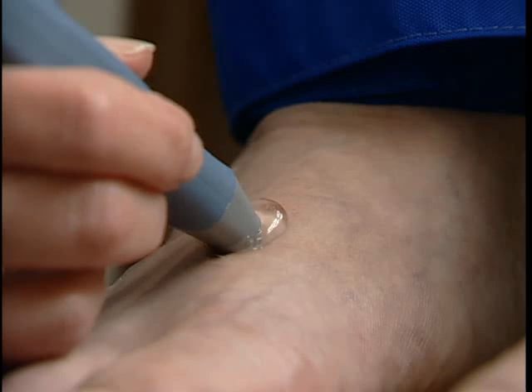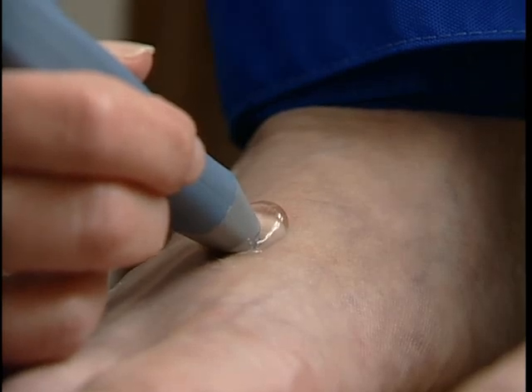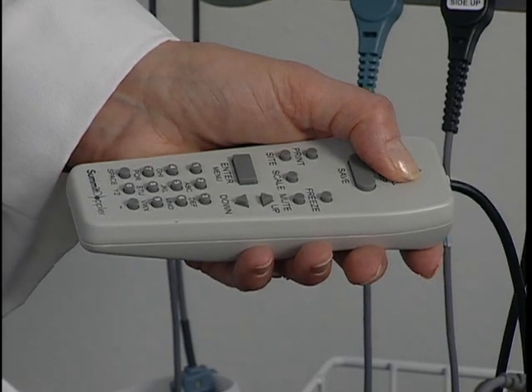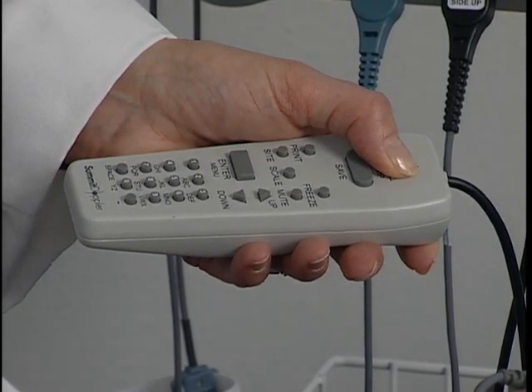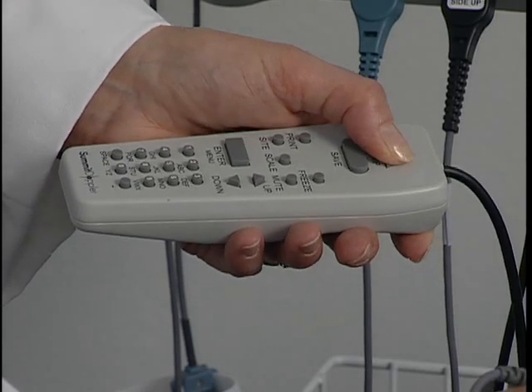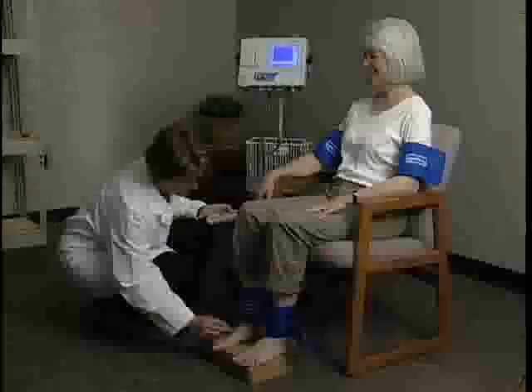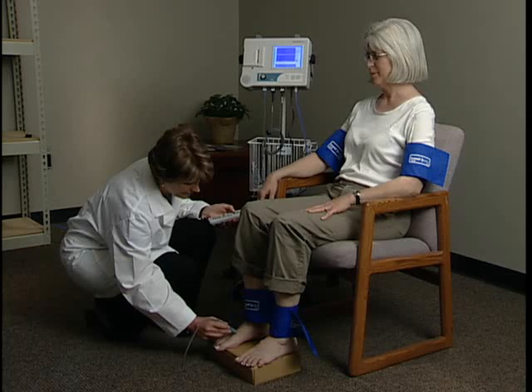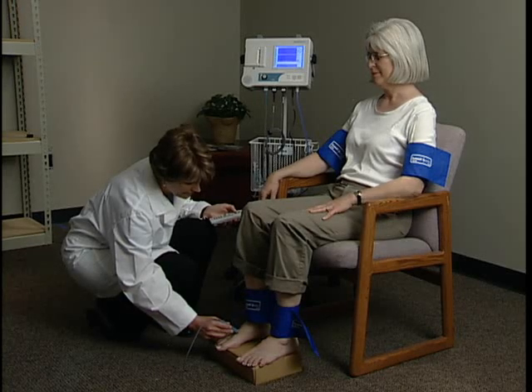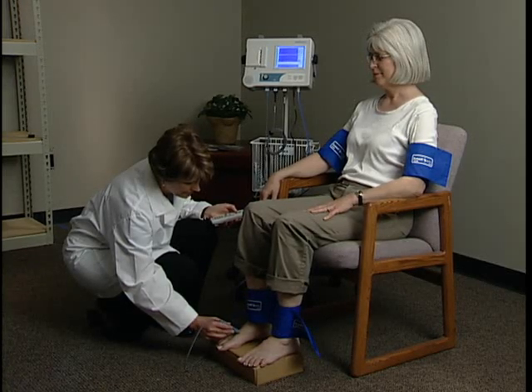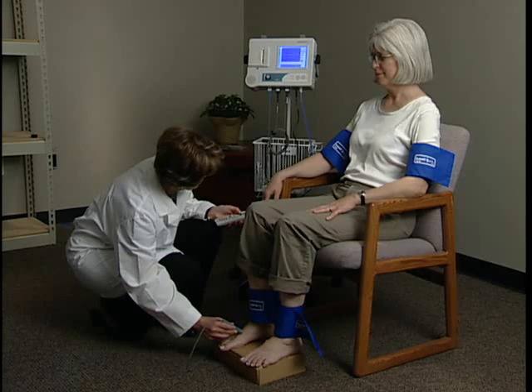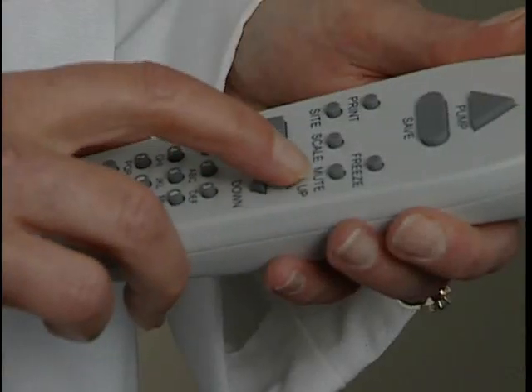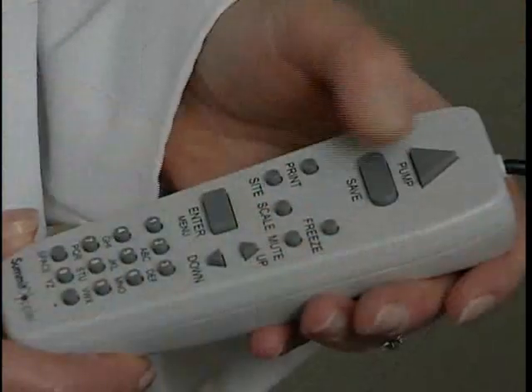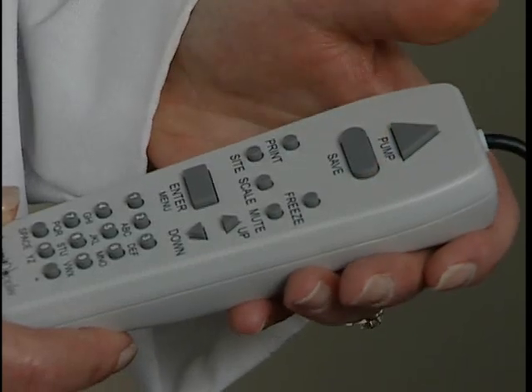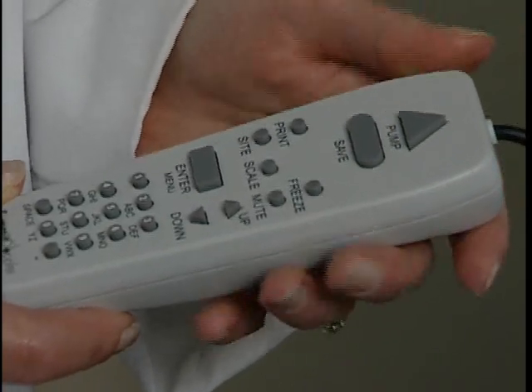While holding the probe steady on the artery, press and hold pump to about 20 millimeters of mercury above the occlusion pressure. Release pump and the cuff will automatically start to deflate. Press Save when you hear the first pulsation return. If you are late pressing Save, adjust the pressure reading by using the up or down key as shown. Press Save to record the systolic pressure, and the marker will move to the next protocol location.